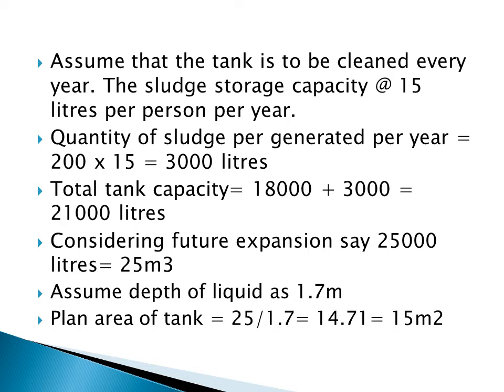The depth of the tank is not given. If not given, you can assume a value from 1.2 to 1.8 meters. Here we assume a depth of 1.7 meters. Therefore, the plan area of the tank equals total volume divided by depth: 25 divided by 1.7 gives 14.71 square meters, which we round off to 15 square meters.